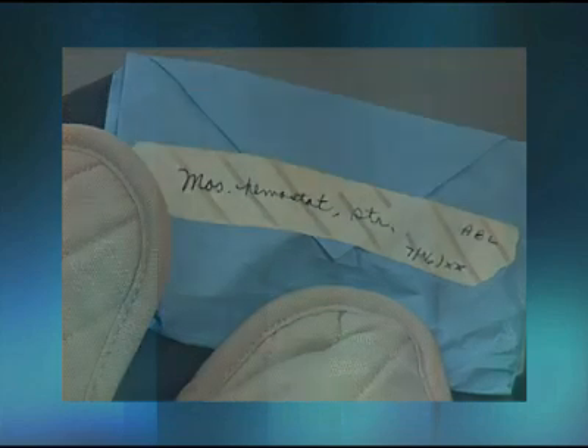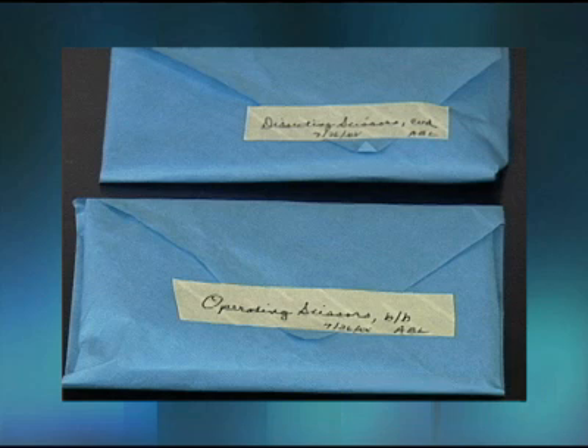After you remove the pack from the autoclave, the chemical on tape changes from white to black, indicating that the pack has been through the autoclave cycle. This prevents mix-ups with packs that have not been processed. Autoclave tape does not indicate that the item is sterile. It only indicates that the pack has been in the autoclave and exposed to steam. Make sure the pack is firm enough for handling, but loose enough to permit proper circulation of steam.